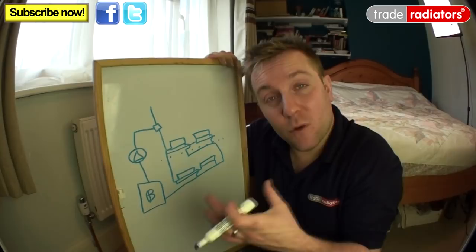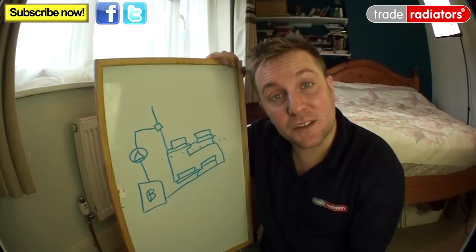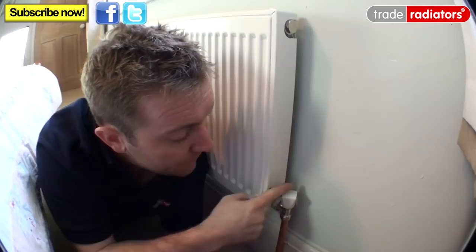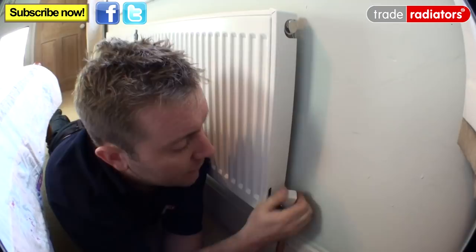So let's show you physically how you actually balance a radiator on a normal heating system. We've got this upstairs radiator here, and we're at the lock shield end now. What I'd usually do is turn this all the way shut — that means clockwise — then make a note of what half a turn would be. So I'm going to give this a half a turn open, and that's that radiator balanced.